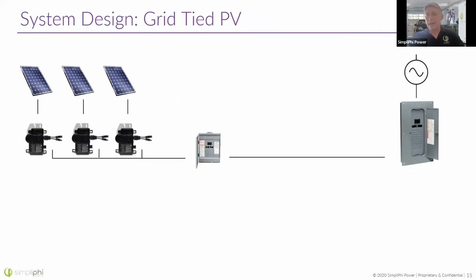Here's why I think AC coupling is so popular: because grid-tied PV is so popular. This is how simple it is to install grid-tied PV. You've got the customer's main panel and you just put on some solar panels and microinverters and a critical loads panel, or even sometimes just this serves as a disconnect. Often there's no loads actually on this panel. It's just serving as a disconnect.